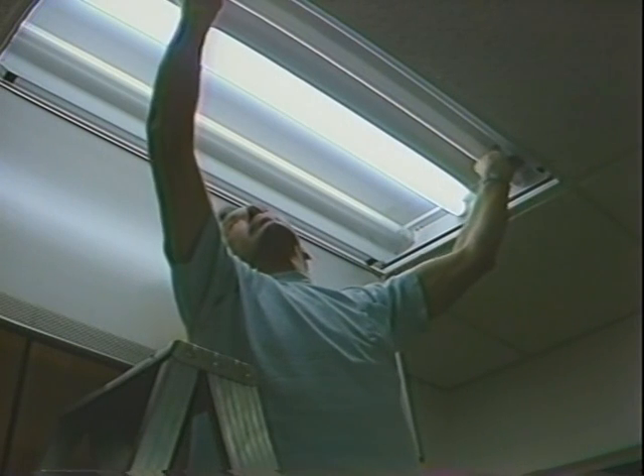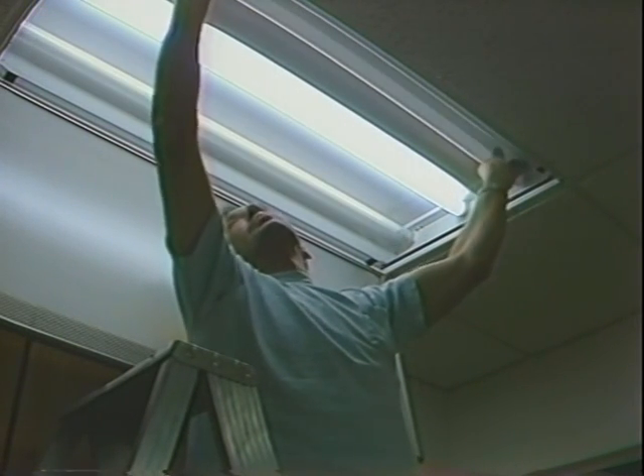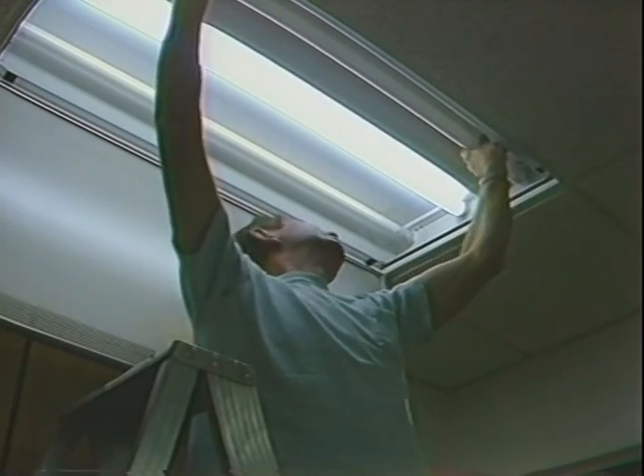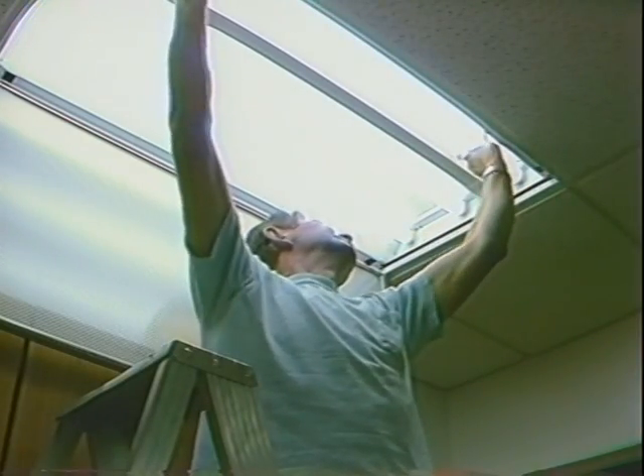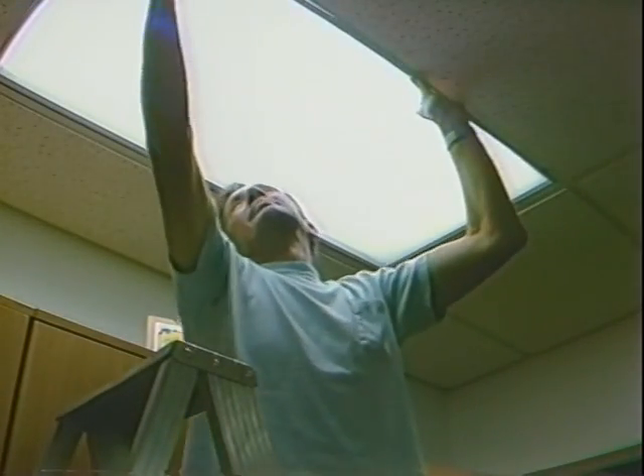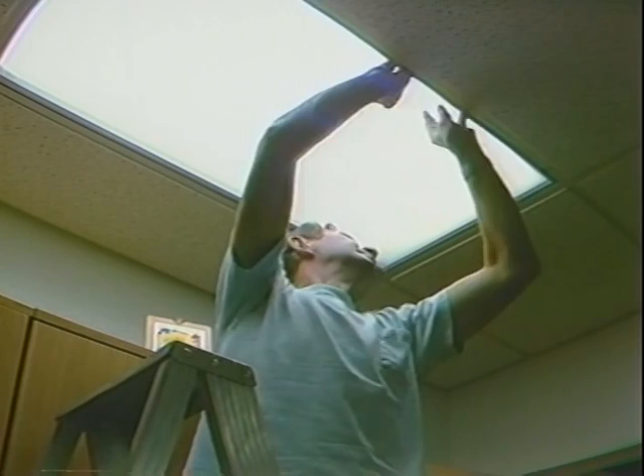If you can downwatt and maintain the same lumens, then you're going to save energy. Existing 40-watt fluorescent tubes inside municipal buildings have been phased out and replaced with more efficient 34-watt tubes and energy-efficient ballasts, a seemingly small change with big results. 6 watts don't make a lot of difference with one fixture, but then you figure that the number of tubes in a building might be in the 5-digit range, 5,000, 10,000 tubes, so then that's 60,000 watts, not 6.